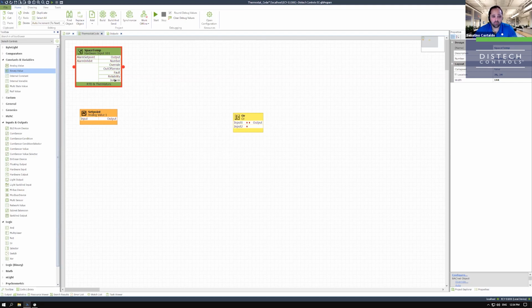But of course, we're already sending that over the network to a recipient. That could be an EC-BOS. It could be any other ECY S1000. It could be another ECY VAV. It could be an ECB 650, you know, with a screen on board. So I could send it to anybody I want over the BACnet network. It's a BACnet alarm.